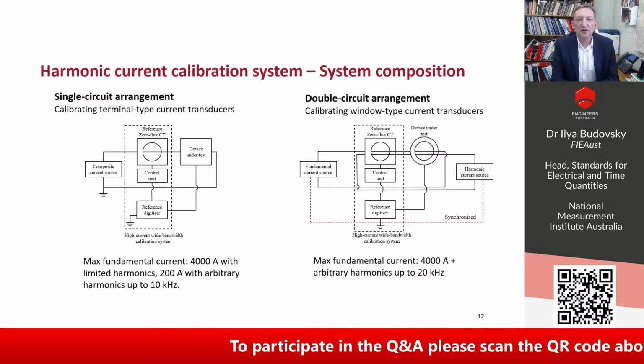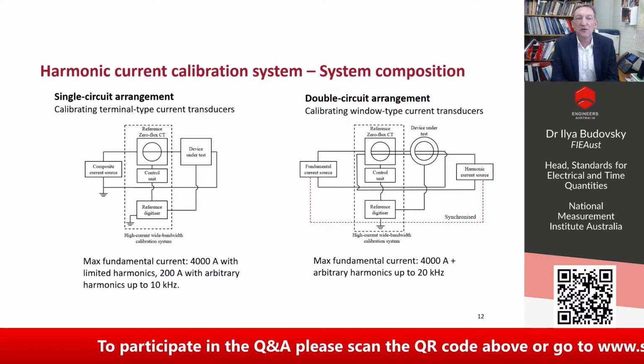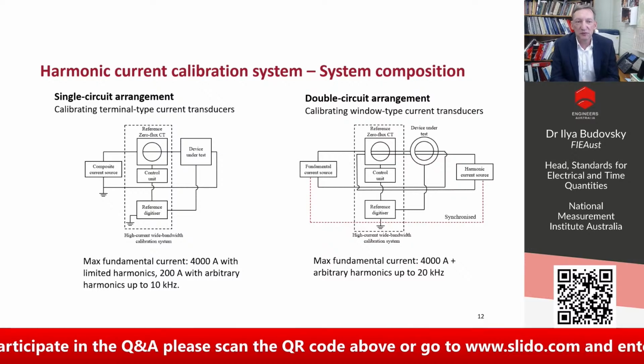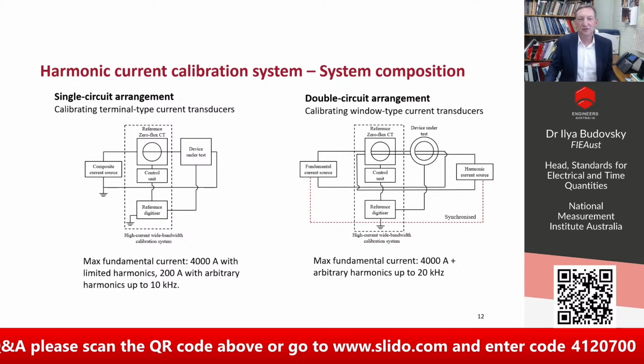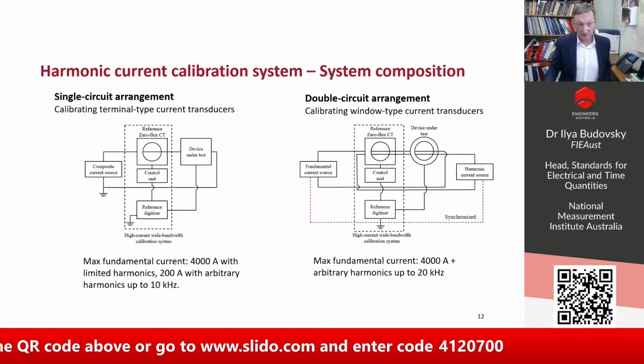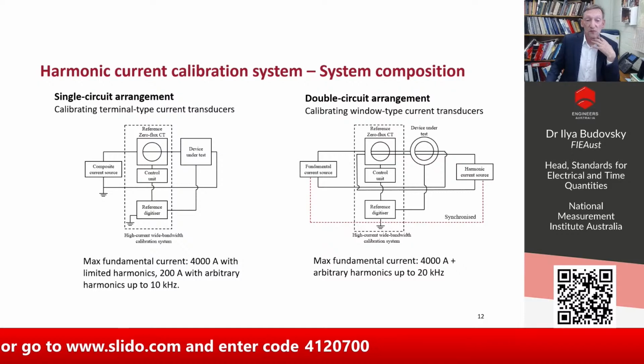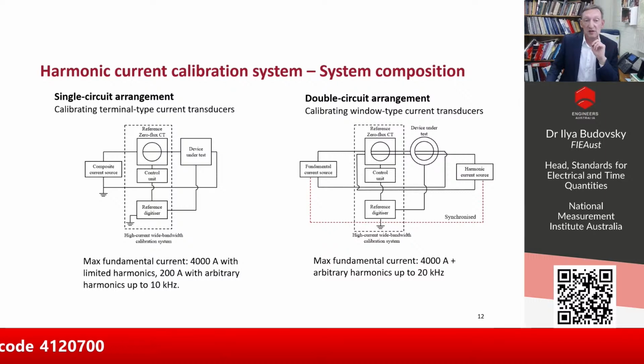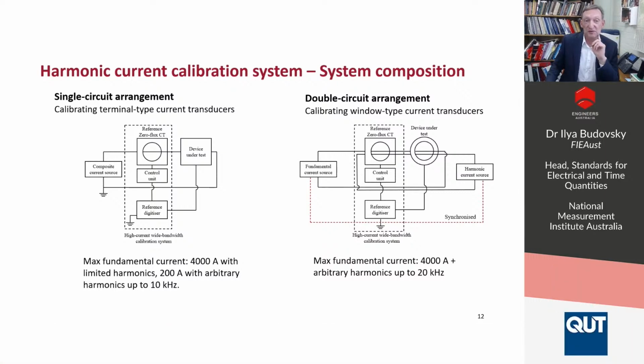On this slide, you can see the two basic arrangements of the calibration system that we use. On the left is the single circuit arrangement. Here, the composite signal containing 4,000 amps and its harmonics is generated by a composite current source, and the current is applied to the reference zero flux CT and the device under test. Then the outputs of the two devices are both measured by the reference digitizer, and the comparison and calibration occur.